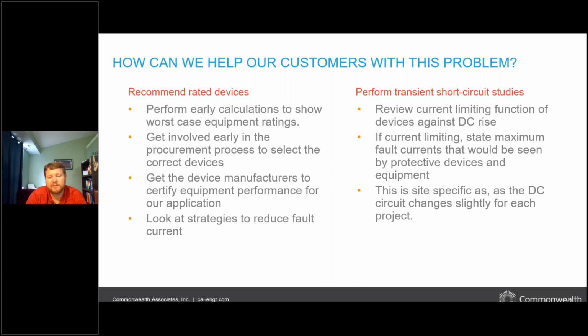We want to come up with preliminary studies that look at what we anticipate the DC fault currents to be, and then try to find equipment early to be able to handle these very large DC fault currents. Alternatively, if we find that equipment ratings are lacking in these areas, then we can look at further study. By going to detailed transient analysis, it allows us to look at the current limiting function of these current limiting fuses and whether they're really going to be effective for our particular application.